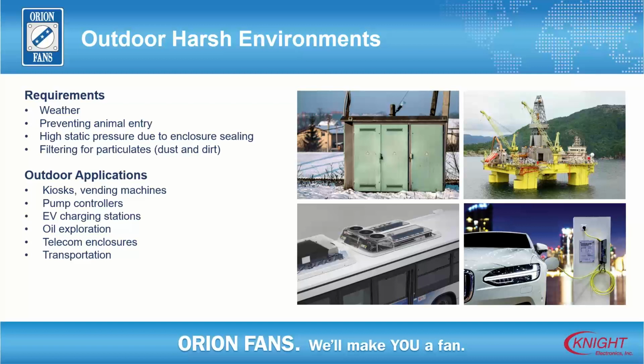One of my customers, every time he opened one up, he had LCD displays in there, and they'd all be completely black until he left it open for a few minutes so they could cool down enough to come back to life. So a fan's kind of a necessary evil in those applications. The outside stuff, if you can't put a fan in it, you'd rather not, but a lot of stuff, especially anything coming to Dallas and Arizona, it's got to have it. Got to have it.